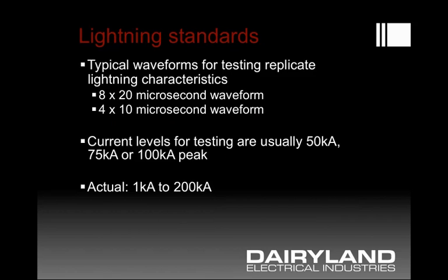There are typical waveforms used for testing products that protect against lightning. The 8 by 20 microsecond waveform, or 4 by 10 microsecond, is just a measure of the wave shape and how fast the rise time is. The current levels that these waveforms reach — that peak value — is typically between 50 and 100 kA as a peak value. In the real world, the values could vary widely from perhaps thousands of amps to hundreds of thousands of amps.